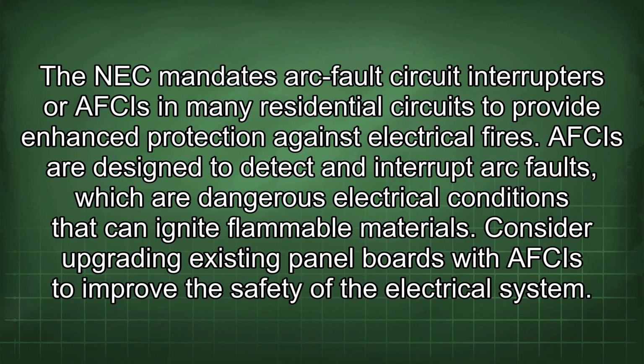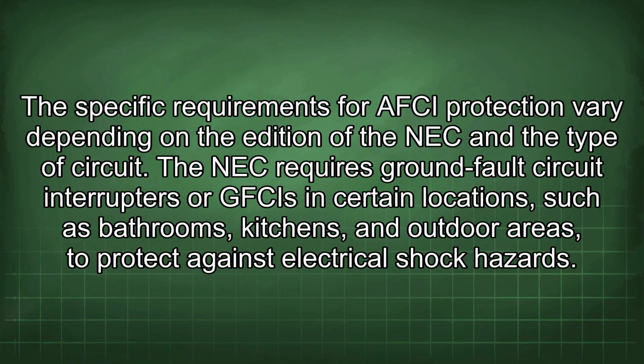The NEC mandates arc fault circuit interrupters, or AFCIs, in many residential circuits to provide enhanced protection against electrical fires. AFCIs are designed to detect and interrupt arc faults, which are dangerous electrical conditions that can ignite flammable materials. Consider upgrading existing panel boards with AFCIs to improve the safety of the electrical system. The specific requirements for AFCI protection vary depending on the edition of the NEC and the type of circuit.